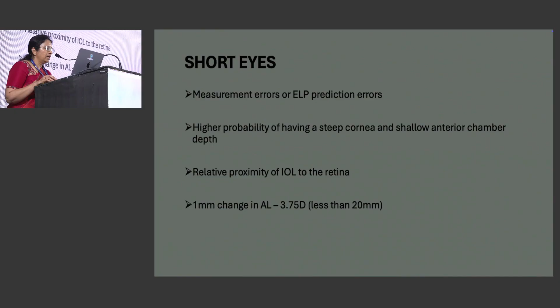Also, IOLs above 30 diopters are expected to be only within plus or minus 1 diopter of the labeled power, whereas those less than 30 diopters are expected to be within plus or minus 0.5 diopters of the labeled power. So in short eyes, since this IOL labeling tolerance is larger, it is more likely that it may not coincide with the actual labeled IOL power.